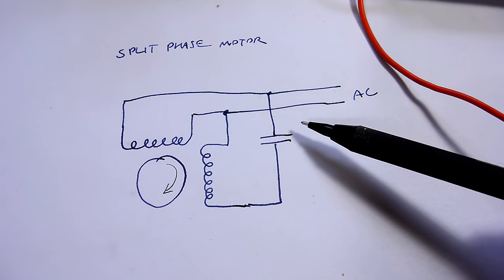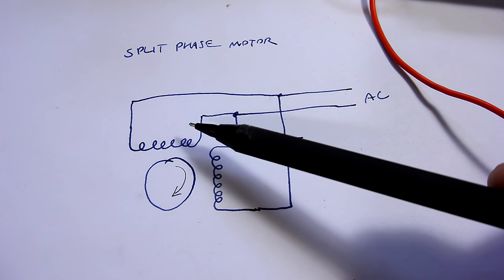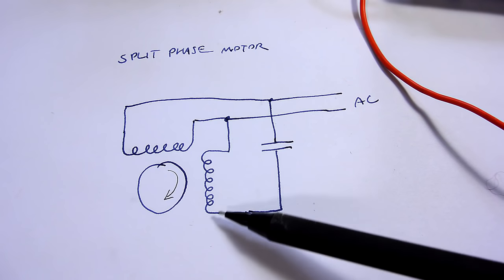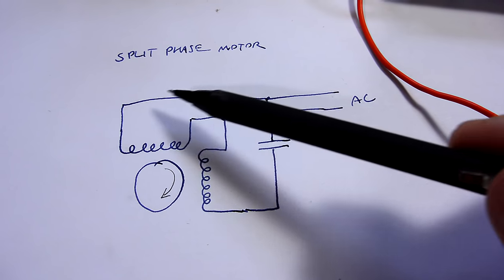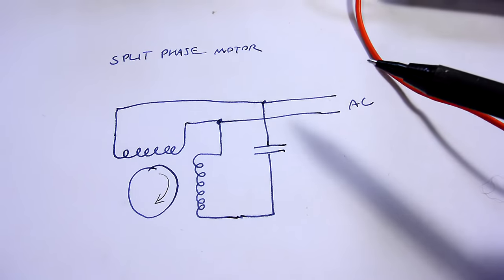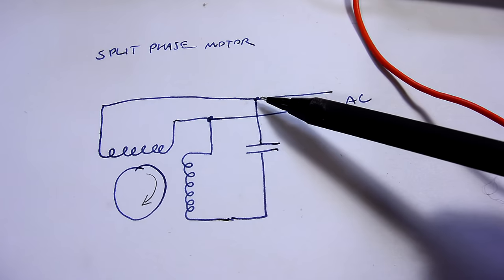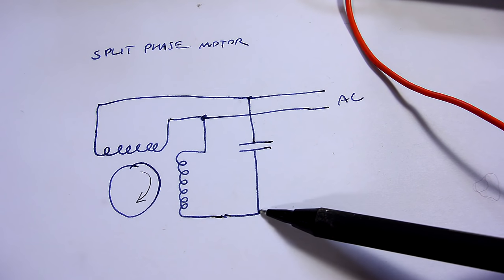Reversing this type of motor is trivially easy. All I have to do is move the AC from directly to this coil to directly to this coil and then through the capacitor the other winding is delayed. So essentially all I have to do is move the power connection from here to here.